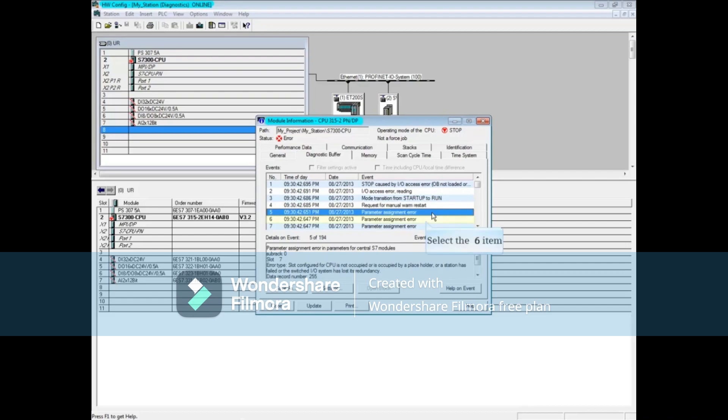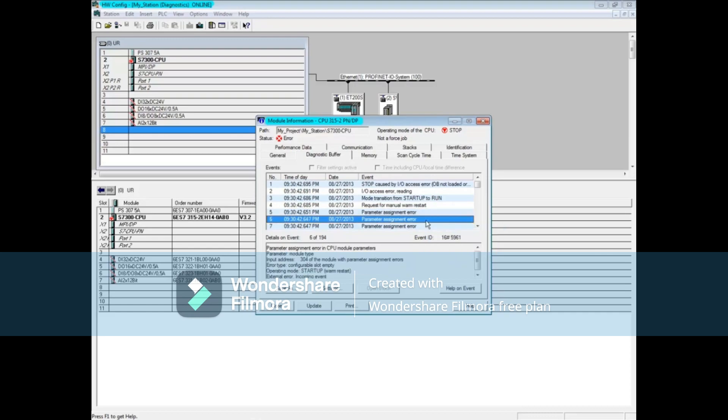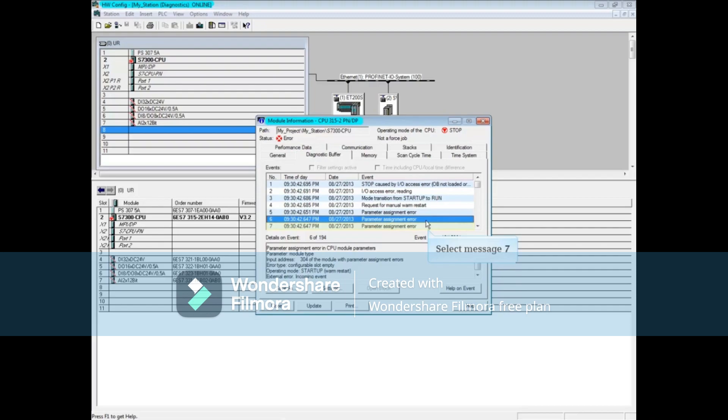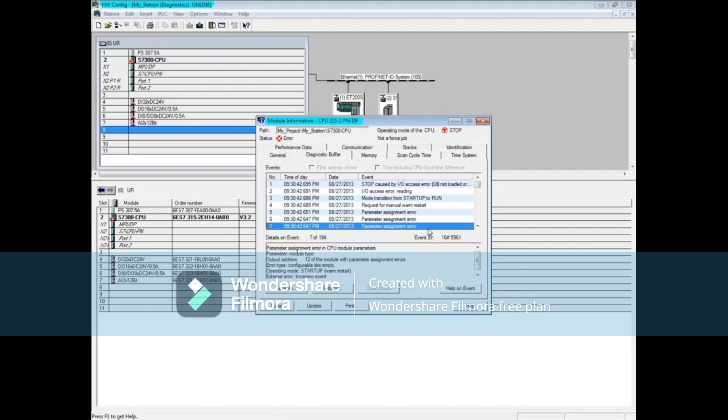Let's check on message 6, which is also a parameter assignment error. This message says there's a problem with the input address 304. Message 7 also says there's a parameter assignment error. There's a problem with output address 12.